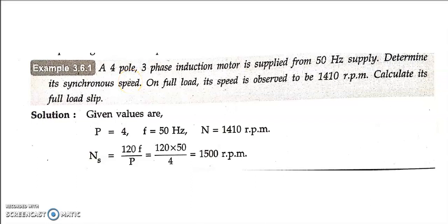Hello guys, we shall discuss problems based on the three-phase induction motor. Here's the problem. A 4-pole three-phase induction motor is supplied from a 50 Hz supply. Determine its synchronous speed, that is Ns. On full load, its speed is observed to be 1410 rpm. Calculate its full load slip.